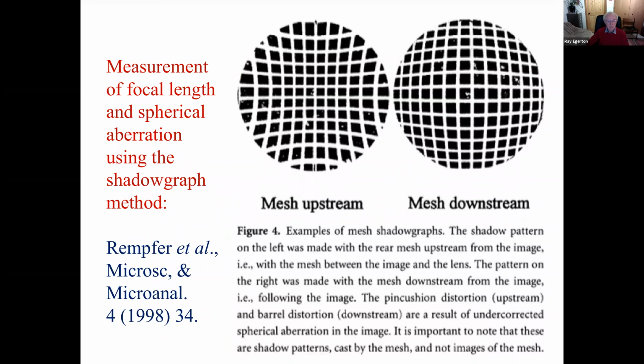In order to characterize these lenses experimentally, we used a procedure that is described in a paper by Rempfer et al. And that consists of placing within the optical column a mesh, and a TEM grid works quite well, at a known position from a beam crossover. And then depending on whether that mesh is upstream or downstream of the crossover, you get an image. It's actually a shadowgraph, an out of focus image, which tells you from the spacing of the grid bars what is the focal length of the lens, and from the curvature of those grid bars, in other words, the distortion in the image, you can get an estimate for the spherical aberration coefficient.